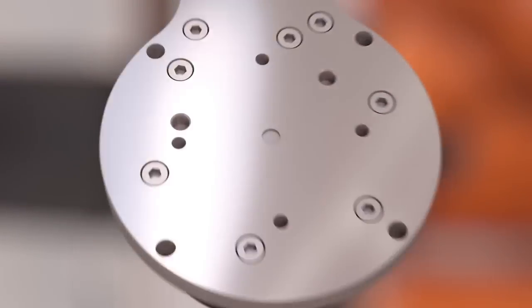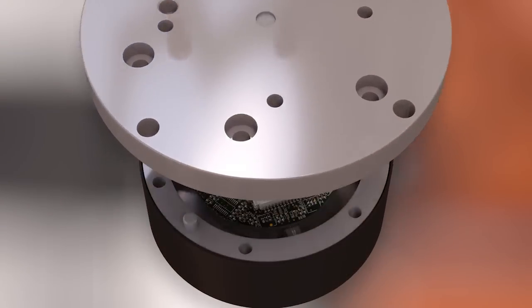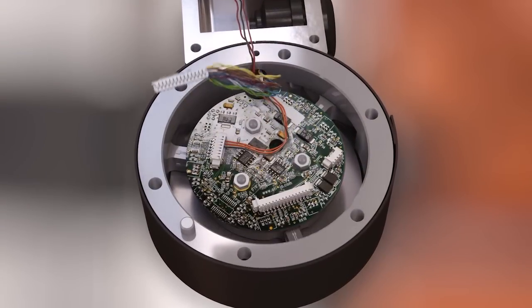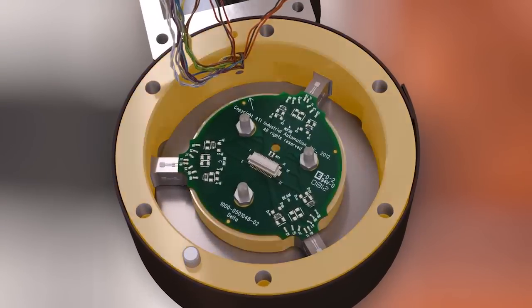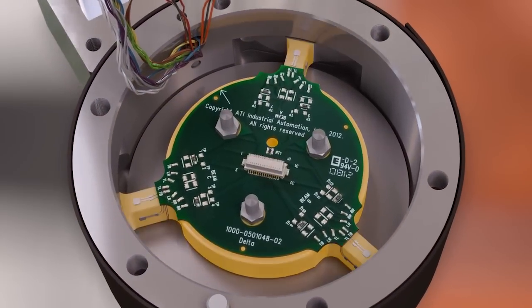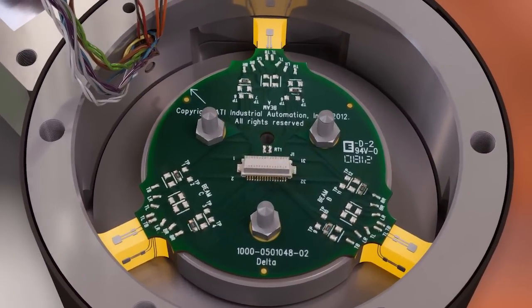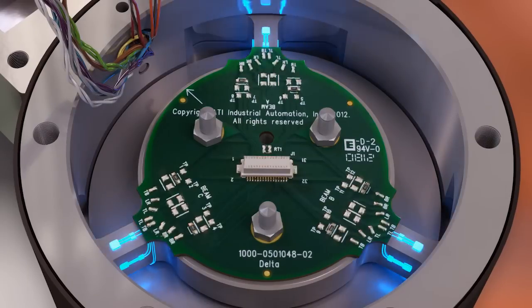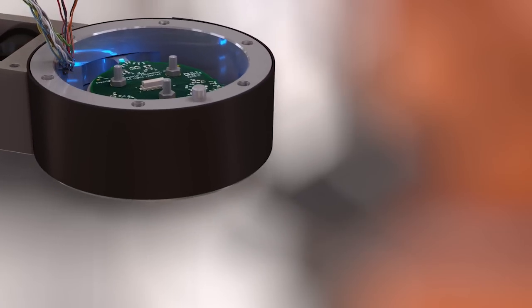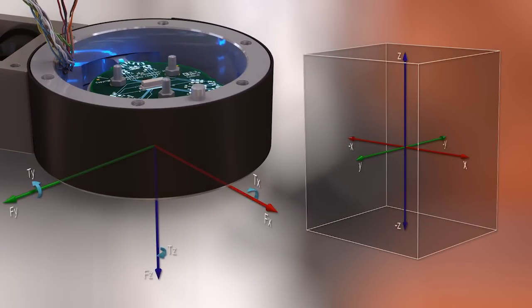When you look inside the ATI force torque sensor, you can imagine it resembles a wheel with an outer wall, with an inner hub, with spokes or beams connecting them. Each beam has four silicon strain gauges that function in pairs to form half bridges. The output of the transducer is six channels of strain gauge voltages. The output is digitized and then converted to forces and torques through a matrix calculation.